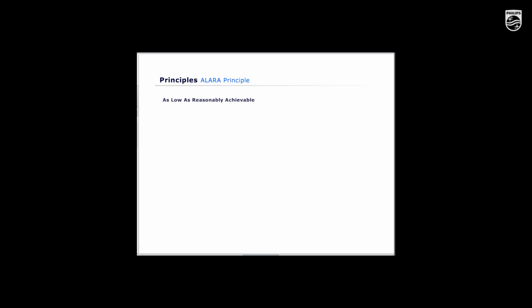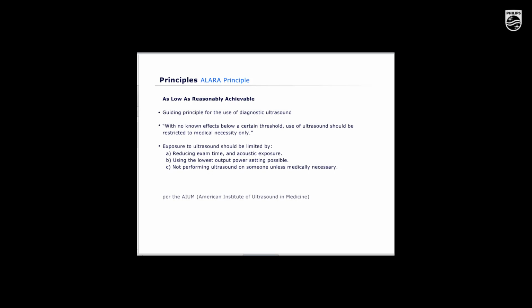There is a principle that helps guide in the reduction of the chances of tissue damage by bioeffect, and that is known as ALARA. ALARA is an acronym for as low as reasonably achievable, and it is a safety principle for the use of diagnostic ultrasound and other diagnostic imaging systems. Some think that reducing exam time is enough to reduce patient exposure to acoustic energy, but in actuality, the dwell time, which is the time a probe is actually on a patient when you are not actively getting an image for diagnostic purposes, is what must be reduced. Even though there are no known effects below a certain threshold, use of ultrasound should be restricted to medical necessity only.